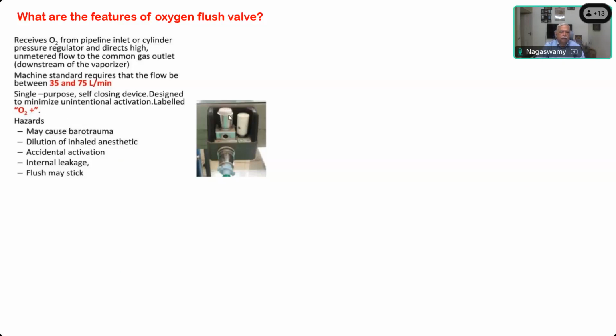This is a push type button. And if this button is not fully released, you will get a slow stream of oxygen going all the time, and that may cause a tight bag situation. Internal leakage also can happen, and the flush may get stuck in some positions by repeated use. So these are all the features of that. What are some unique features of the oxygen flush? These are all regular features.